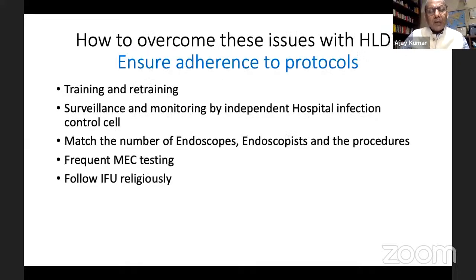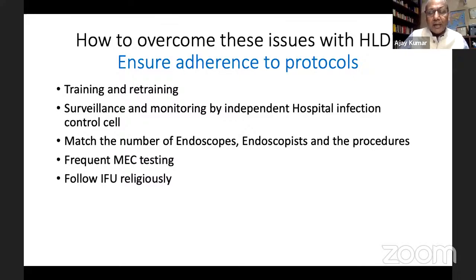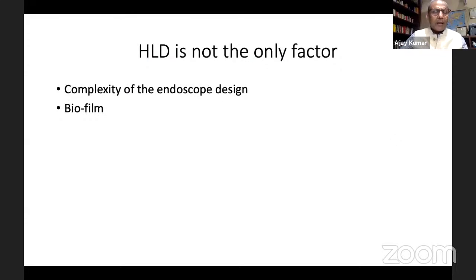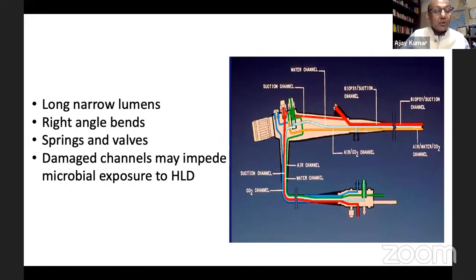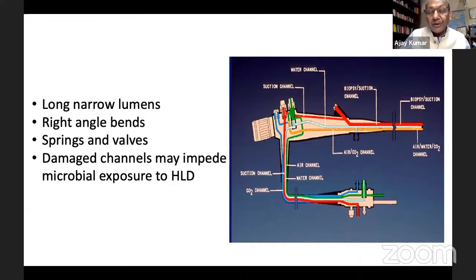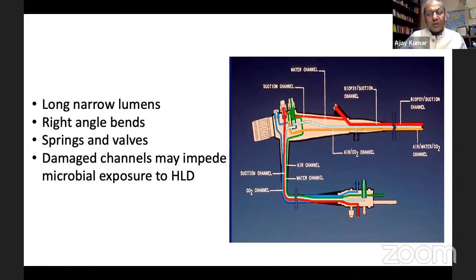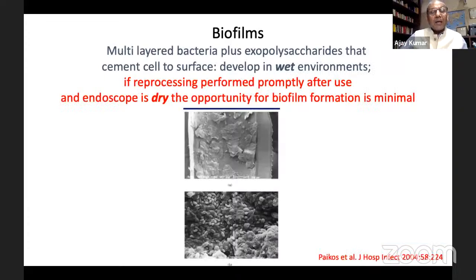We keep blaming HLD and asking for its replacement — but as a corollary, it is like blaming traffic lights when you don't follow them and meet with an accident. If everybody starts following the traffic lights, things will improve. Beyond microbial load, other factors inherent in endoscope design include complexity — long narrow lumens, right-angle bends, springs and valves — and the issue of biofilm. Whatever method you use, whether HLD or sterilization, these factors are common to both and must be addressed.